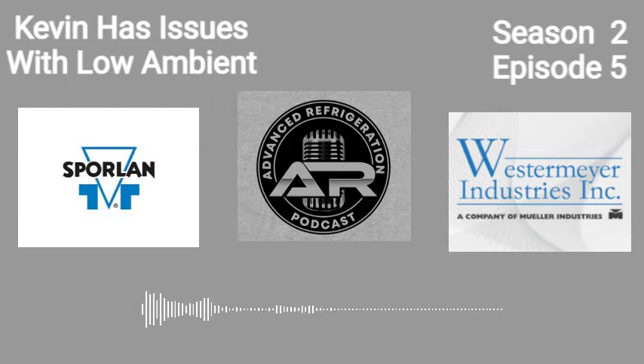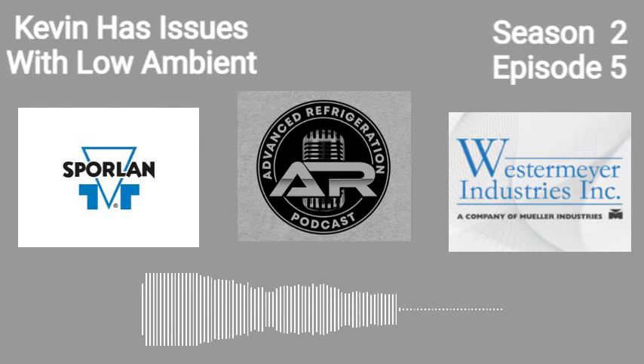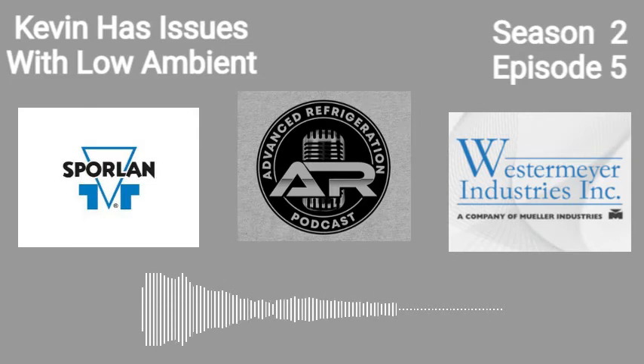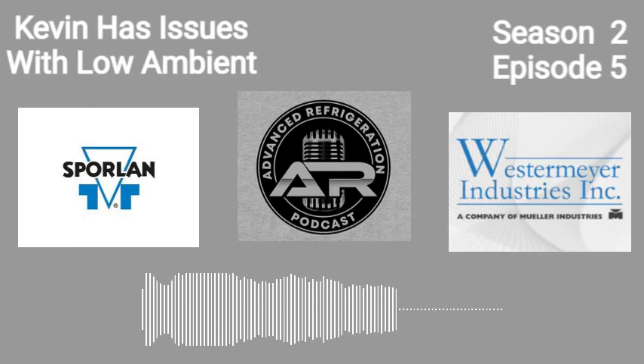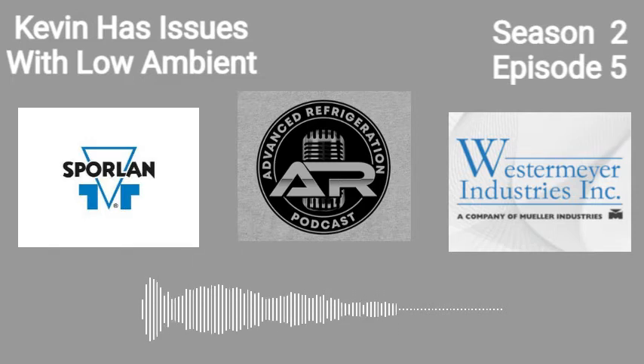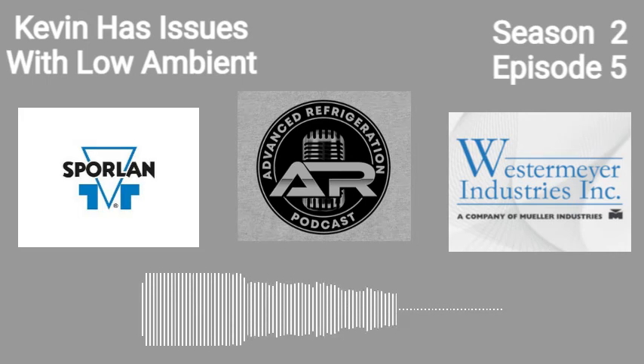Oh no. So they tried it multiple times. They couldn't get the condenser to build up pressure no matter what they did. They could not get any of the gas out of it. They couldn't get it to run. Well, finally he calls me back, and this is an EEV store. I asked him, what are the EEVs doing? This is the first time I've ever seen this. He goes, oh, they're both closed. Oh shit. Killer. I go, okay, are they closed because the compressor shut down? We're going through it, we're looking through it. No, they're closed because superheat's 0.